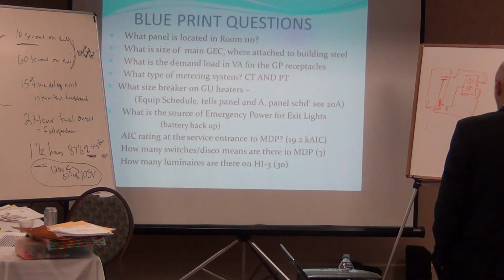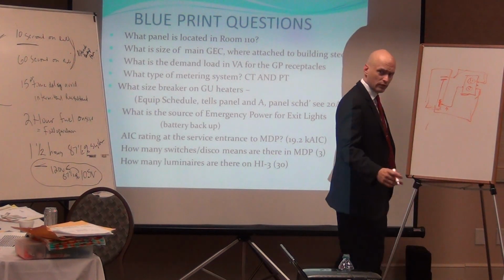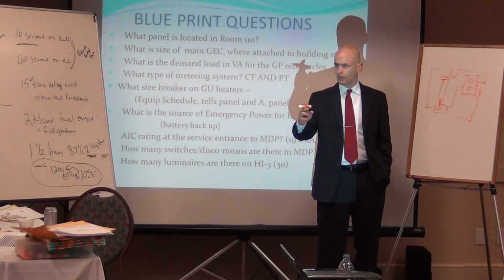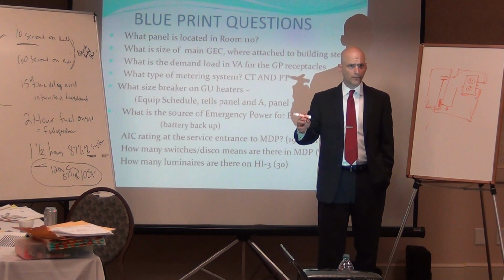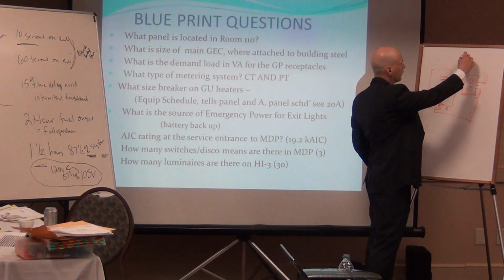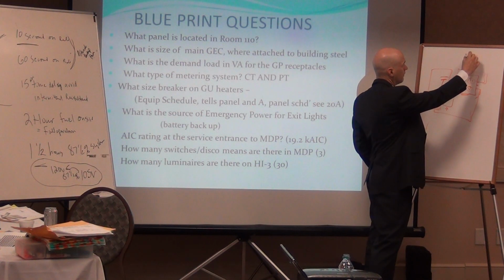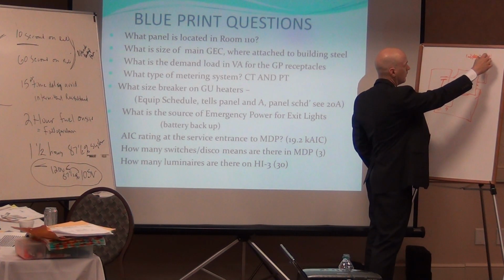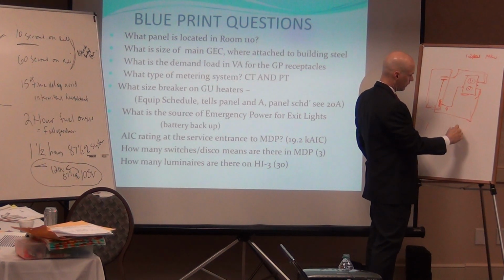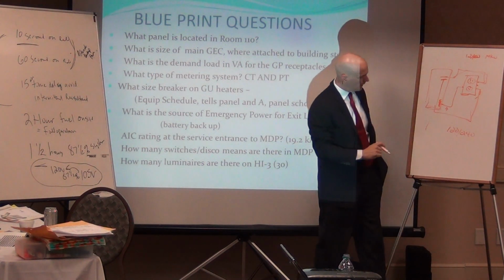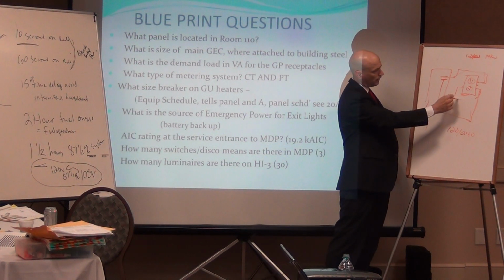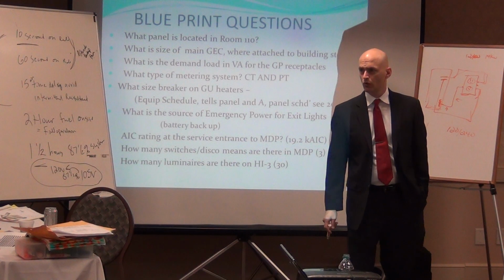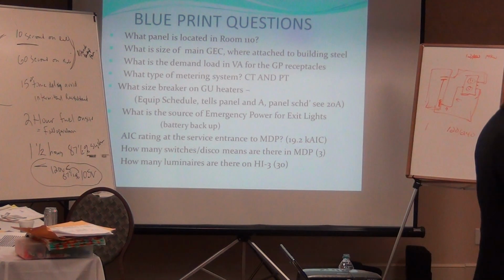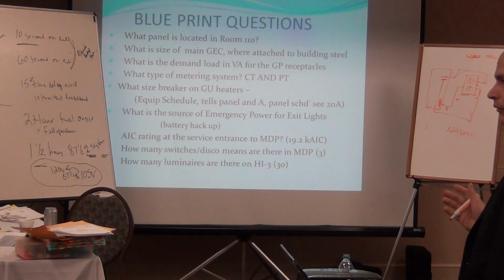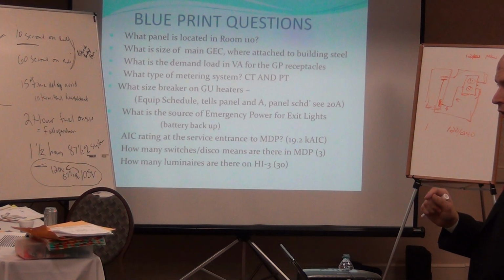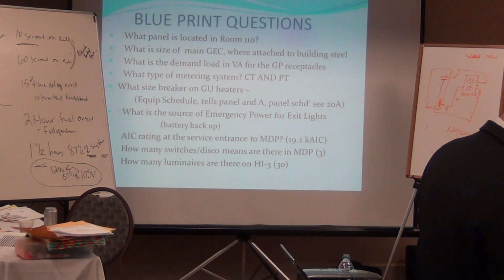So the test question that gives an example of this was one I was asking, I guess it was you that had, did you have the two water heaters? We had the two water heaters, multi-wire branch circuit. It was two water heaters, a 12 kW, so 12 kVA, and a 14 kVA. Telling you it was a 120/240 volt service, and they wanted to know what was the amperage draw there on the neutral. The first 12 kVA on both sides of that is going to cancel each other out, right? We just carry the net difference between those two numbers. So what would be the load then on that conductor?